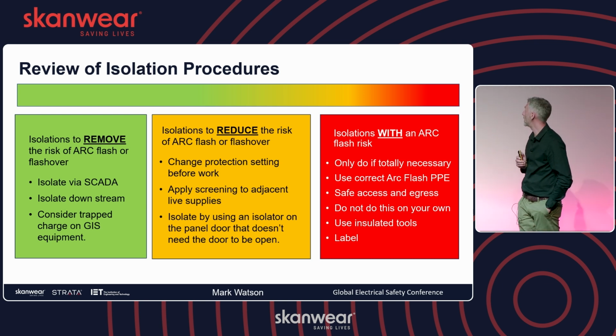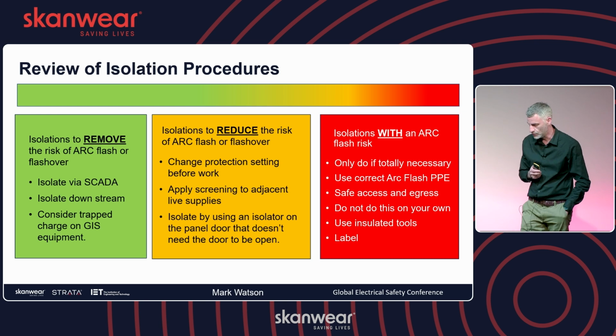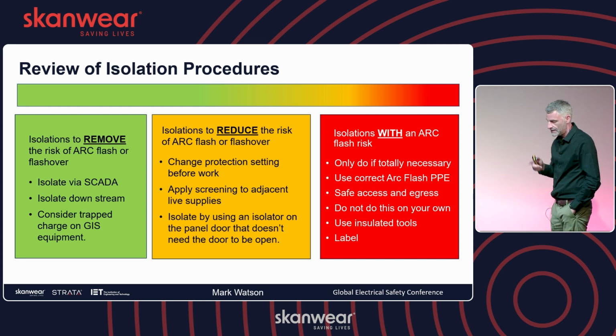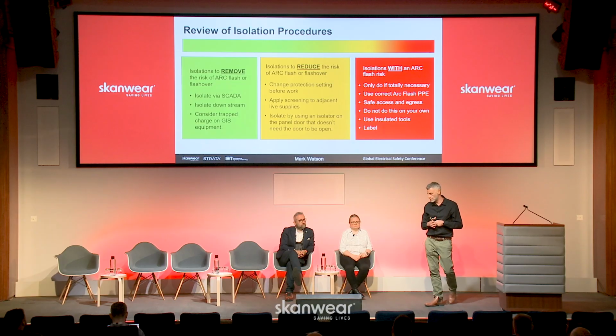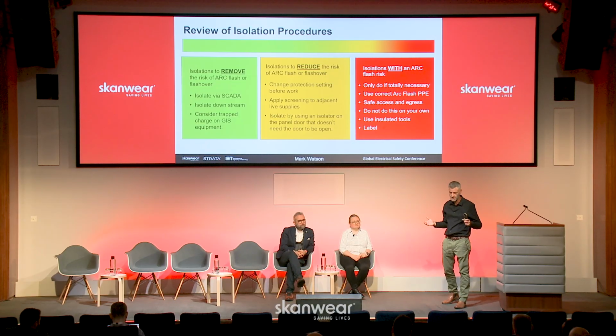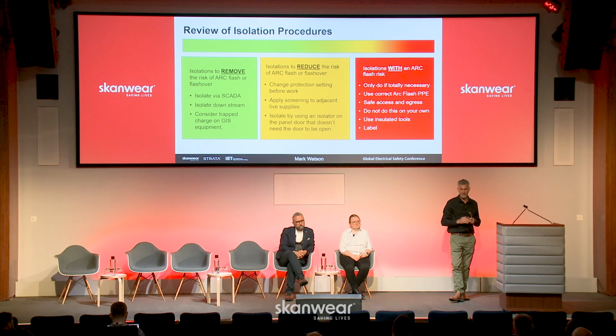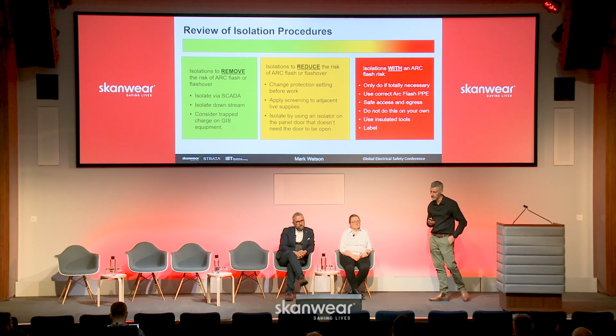Insulated tools and the correct labels - labelling, we mentioned many times yesterday. Understand the arc risk, understand the values, understand the PPE required. If that's on a sticker on the front of the panel, then everyone can comply. As for insulated tools, if there's a risk you could drop something or touch something, it's just good practice to use the correct tooling.